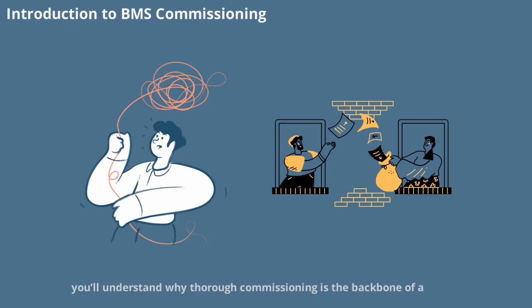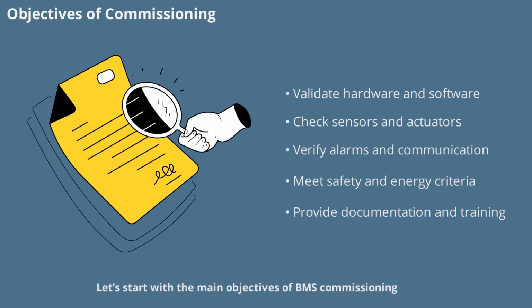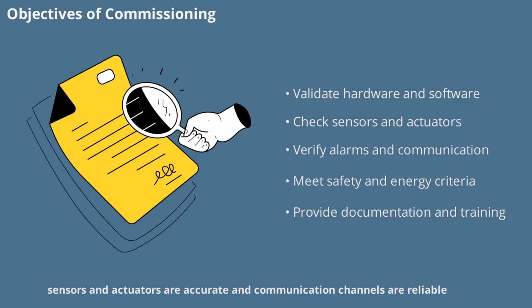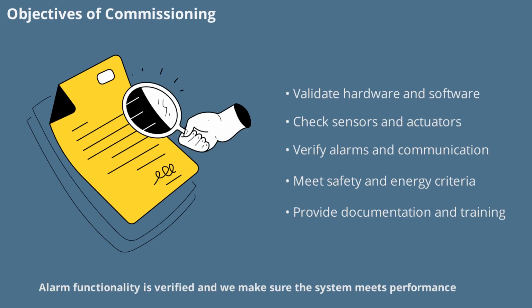By the end, you'll understand why thorough commissioning is the backbone of a reliable BMS and how it sets the stage for long-term performance. Start with the main objectives of BMS commissioning. The goal is to validate both hardware and software installations, ensuring that every component is in its right place and working as intended. We check that all sequences of operations are functioning, sensors and actuators are accurate, and communication channels are reliable. Alarm functionality is verified, and we make sure the system meets performance, safety, and energy efficiency standards. Finally, providing clear documentation and training to the client is a must, setting them up for successful operation.